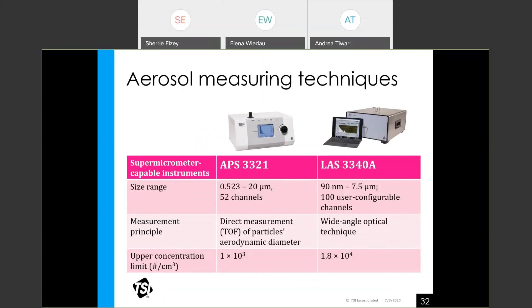Two other instruments are briefly mentioned: the aerodynamic particle sizer (APS) and the laser aerosol spectrometer (LAS). The APS directly measures aerodynamic size using a time-of-flight technique, sizing particles from 0.523 to 20 micrometers with an upper concentration limit of 1000 particles per cubic centimeter. The LAS has a wider size range of 90 nanometers to 7.5 micrometers using an optical technique; while the APS has fixed size bins, the LAS allows user-configurable size channels. Peer-reviewed literature demonstrating use of each for e-cigarette aerosol is shown near the end of the presentation.